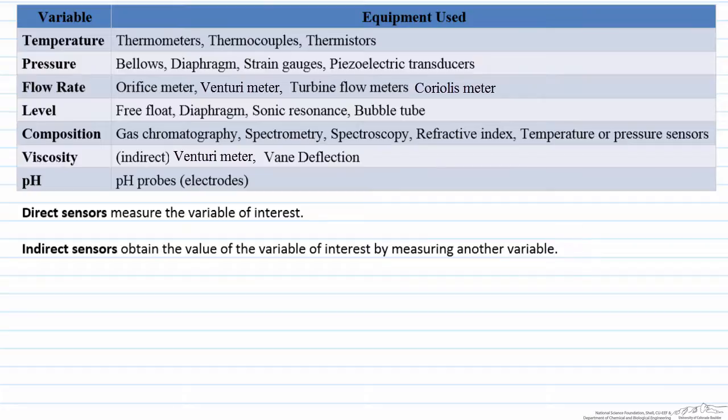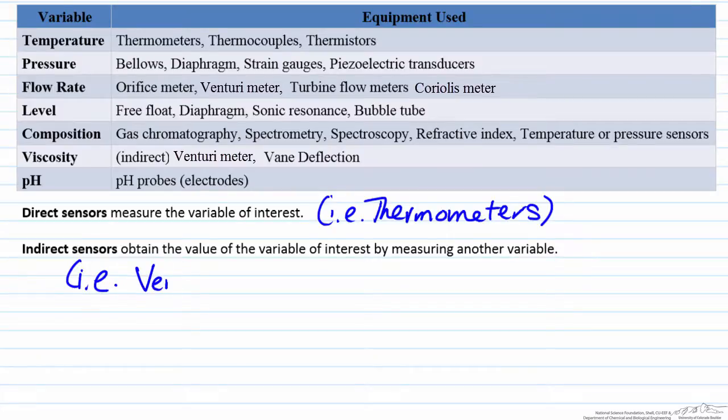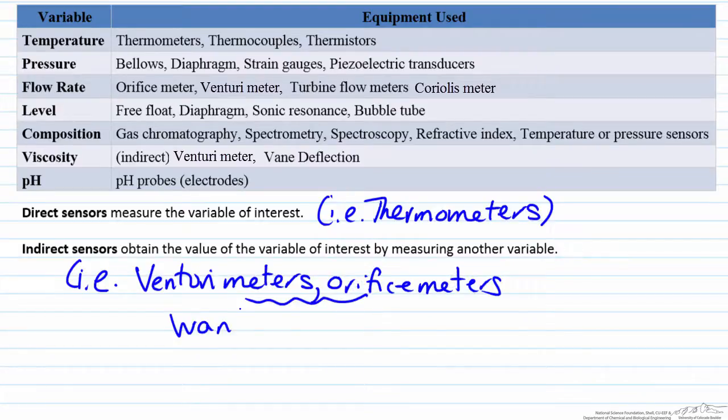Some examples of direct sensors would be thermometers. A couple examples of indirect sensors are many flow sensors that act as indirect sensors, such as venturi meters and orifice meters. Because what they're doing is we want the flow rate, but what they actually measure by taking advantage of Bernoulli's principle, they can measure the pressure drop between two particular points and use Bernoulli's equation to find the flow rate.